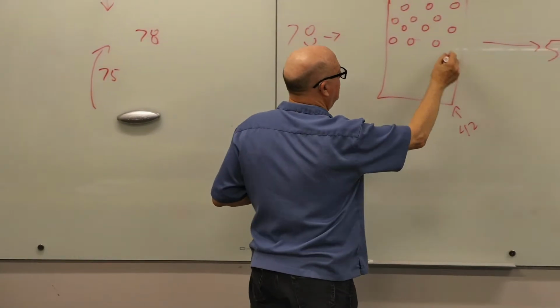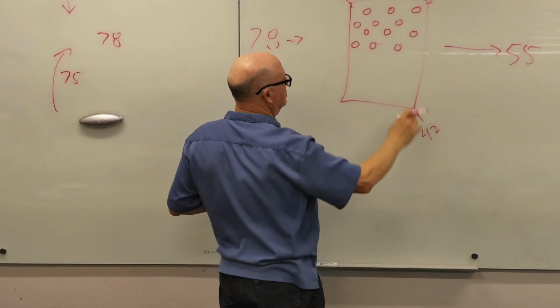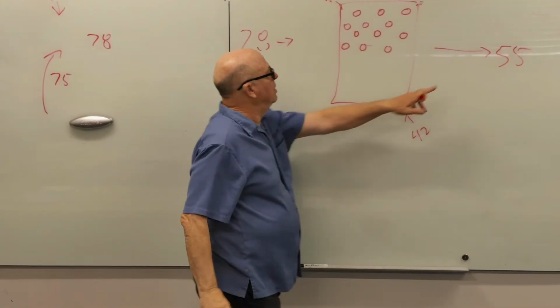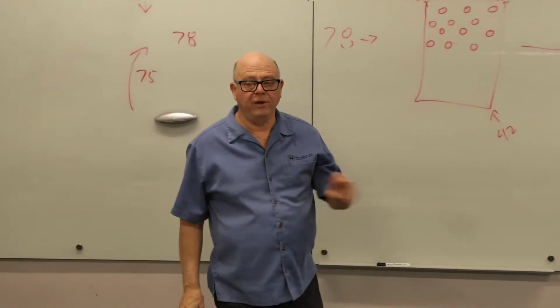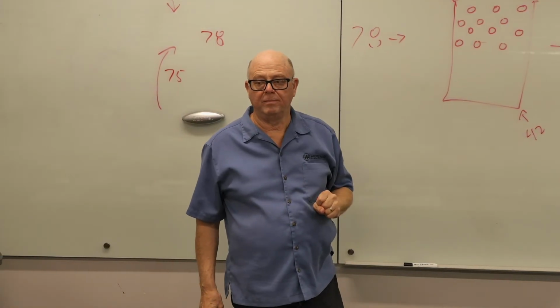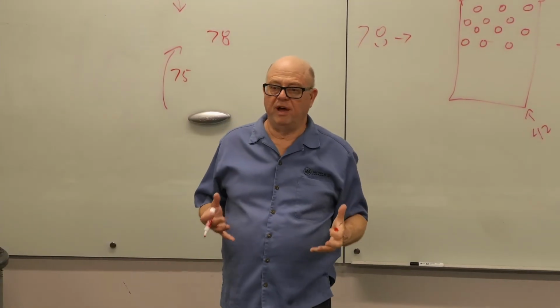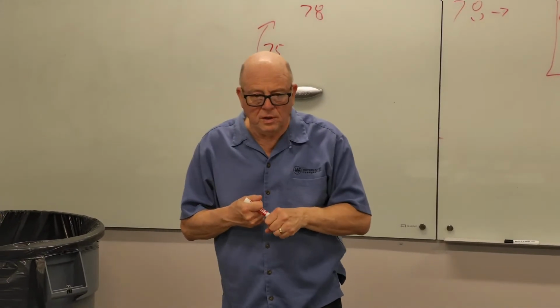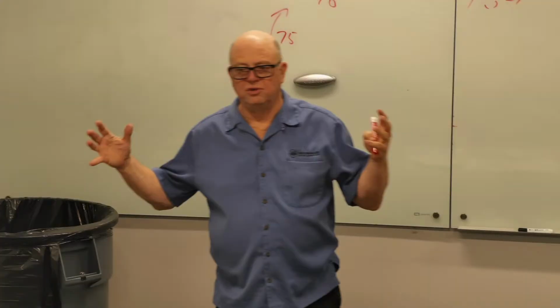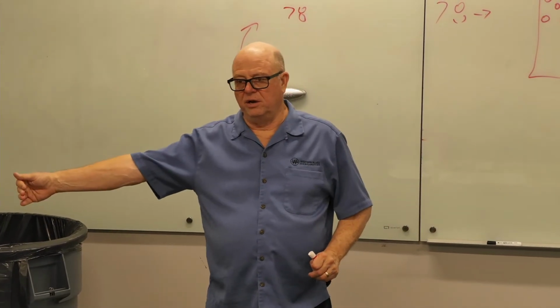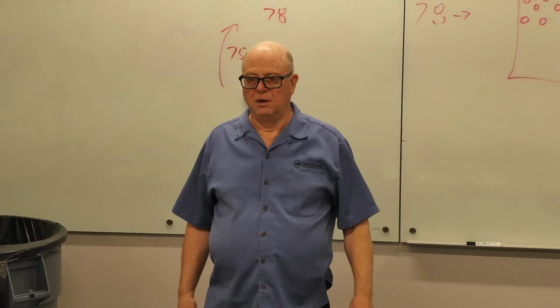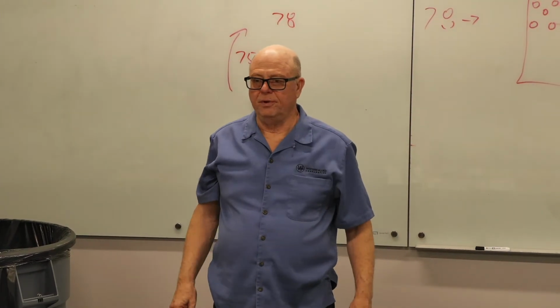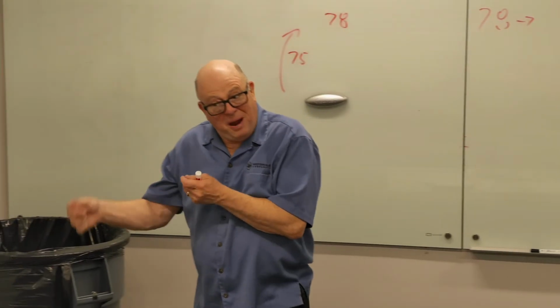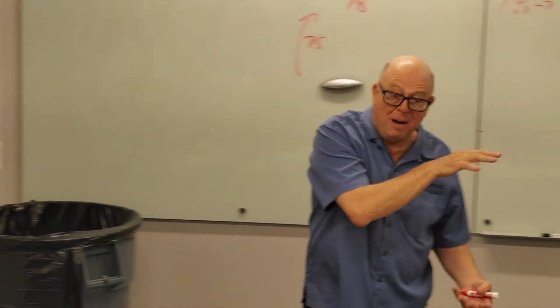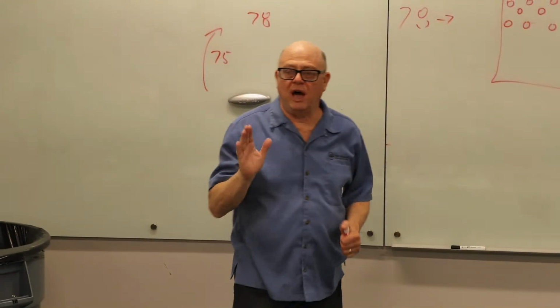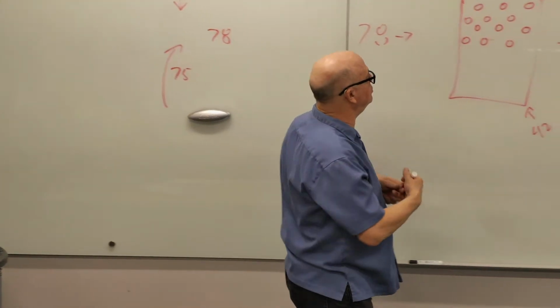So the 42-degree water is on the leaving end. I drew this piping it in the bottom, but there's no magic of piping it in the bottom. The manufacturers use the same coil for a left-hand air handler as they do for a right-hand air handler. They just flip the coil over. So if it's piped from the bottom as a right hand, it's probably piped from the top as a left hand, right? So you've always got to pipe it counterflow. This would be a 6-row coil.